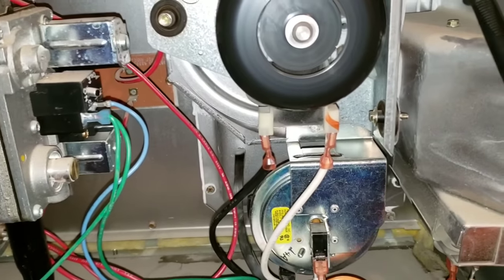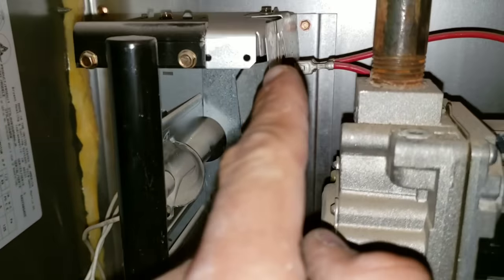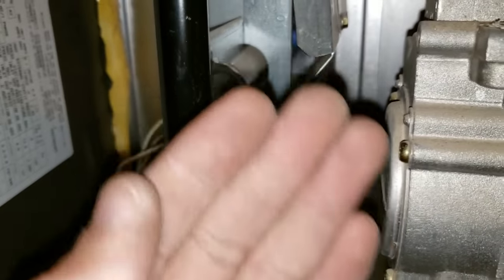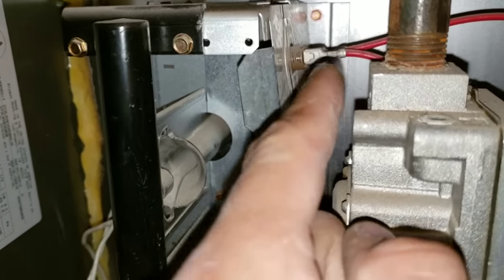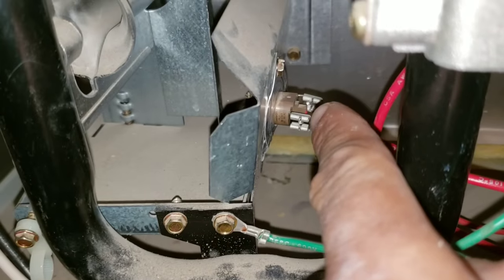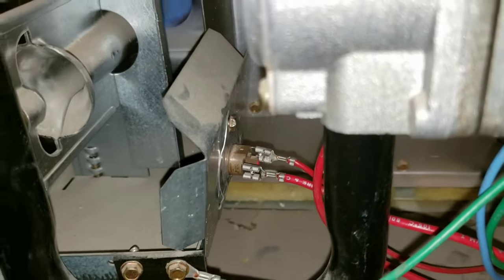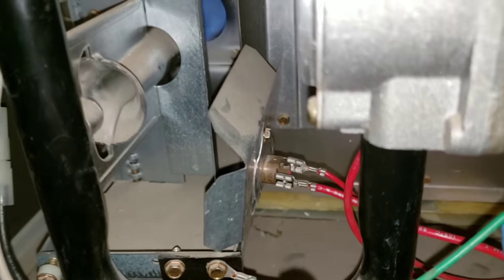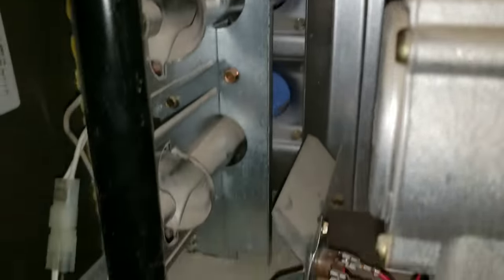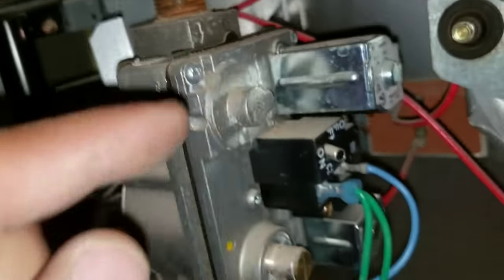Here are a few things worth noting before we end this video. If you look here where my flame is, I do have two flame rollout switches. If for some reason the flame rolls back and touches the switch, that will automatically cause the system to turn off. To fix this, there is an manual reset button here in the middle — you can see the red right there. You can go ahead and just reset it. If you're unable to reset it, at that point you'll have to do a continuity test on each of your switches to make sure that you have continuity. In the back, we have two flame rollout switches as well as a sensor here in the back — they are all interconnected.